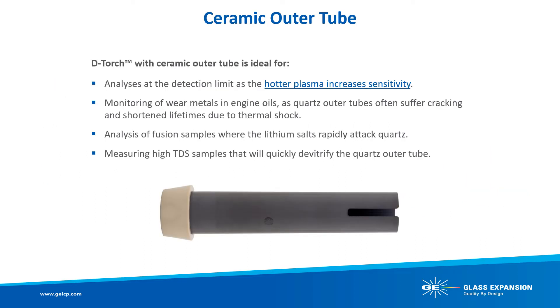Glass Expansion pioneered the design of ceramic torches more than 20 years ago. Using a ceramic outer tube on your ICP torch provides a hotter, more robust plasma, which reduces matrix effects and improves sensitivity and detection limits. Compared to a quartz outer tube, the ceramic outer tube has a much longer lifetime, greatly reducing maintenance and downtime due to torch failure. A fully ceramic D-torch is now available for a wide range of ICP models including Agilent, PerkinElmer, Spectro, and Thermo Fisher Scientific. We have selected the fully ceramic D-torch for our Aqueous HP-SIS with a 2 mm ID quartz injector to achieve optimum sensitivity and detection limits.